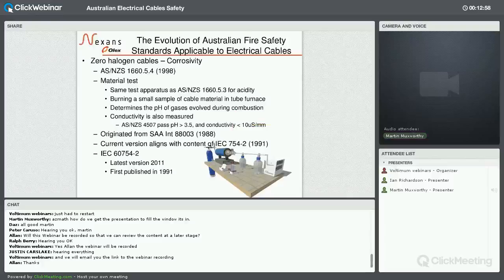Same test setup is used, and these are described by another group of AS 1660 Part 5 standards. This particular one is Part 4, the previous one was Part 3. So again, these are all based on the IEC standards. These are derived from IEC 754, originally published back in 1991. So what we're finding the Australian standards are doing these days is, in a lot of cases, adopting the entire content of the IEC standards. Some of them align, like I've got indicated here. Some of them are adopting the entire content. In other words, it's a word-for-word adoption of the IEC standard.